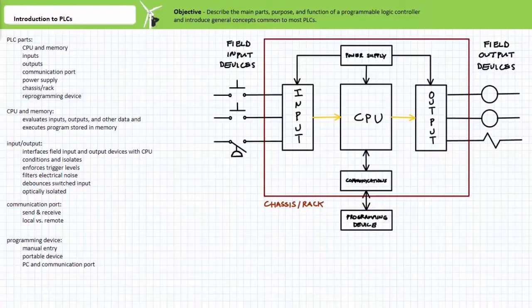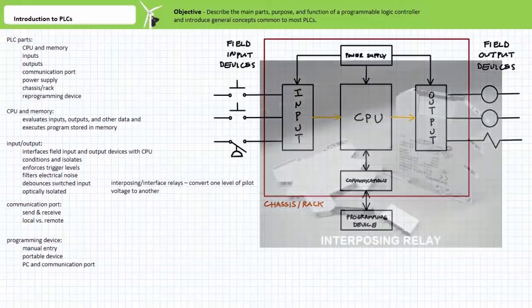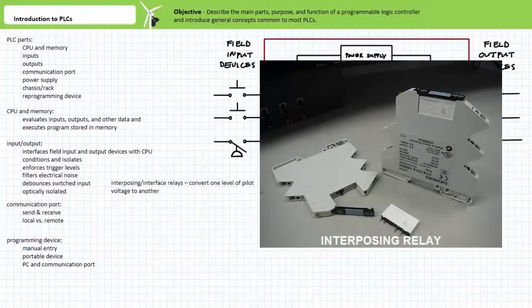Input or output from a PLC can either be DC or AC. Common flavors of pilot level voltage include 24 volt DC and 120 volt AC with a progressive movement towards devices favoring the safer 24 volt DC requirement. Field inputs and output devices must be compatible with a PLC's operation voltage and if not necessitate the use of interposing relays that translate one voltage flavor to the other.